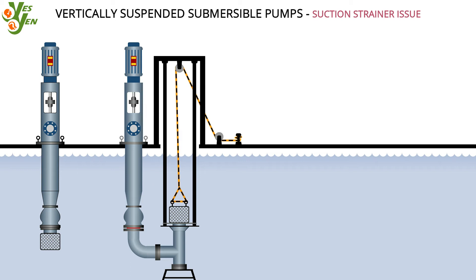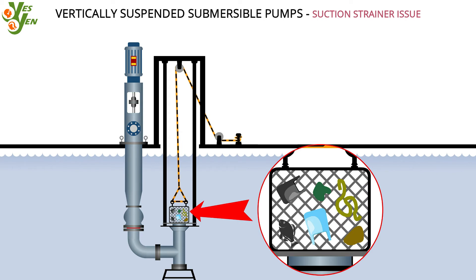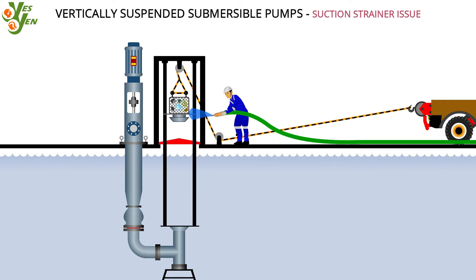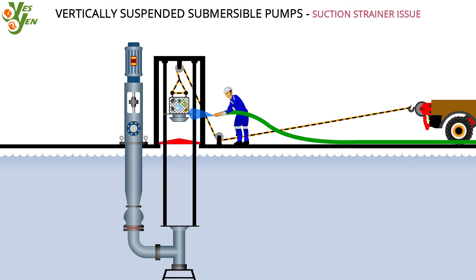The following pump modification gives a way out. The pump suction is extended as shown, and the strainer is repositioned inverted. Whenever strainer cleaning work is warranted, the strainer can simply be lifted; after cleaning it is lowered back to its position, completing the job. The strainer is designed to sit on the respective flange without any bolting. The strainer flanges are preferably conical to ensure concentric positioning. A tie rod ensures the proper positioning of the strainer onto its location.